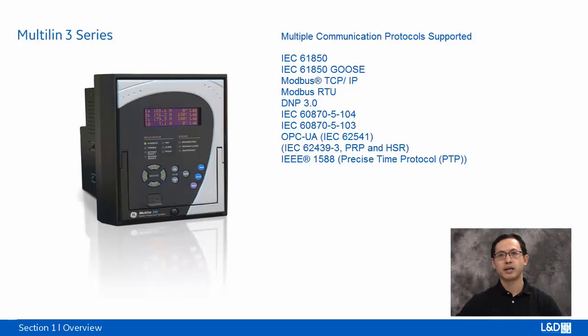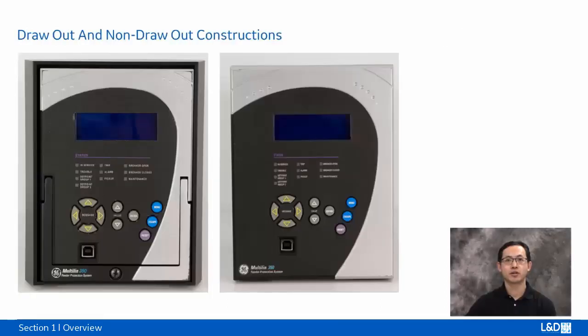3 Series relay warranty is 10 years, as with all GE Multilin relays. Types of the front panel for 3 Series: draw-out and non-drawout. Both can simplify the commissioning and maintenance. For the draw-out type, the relay can be removed from the chassis with the wiring still connected. For the non-drawout type, the wiring can be pre-wired to the Euro-style terminal blocks, then plugged into the relay.